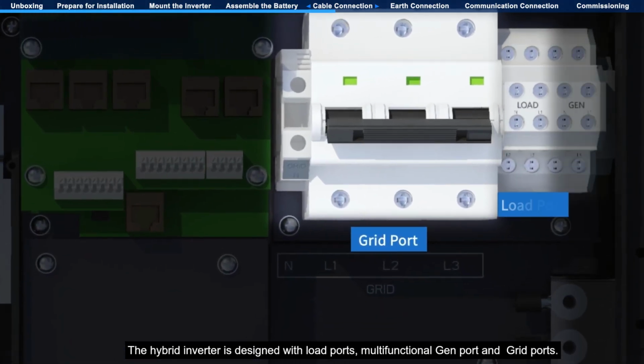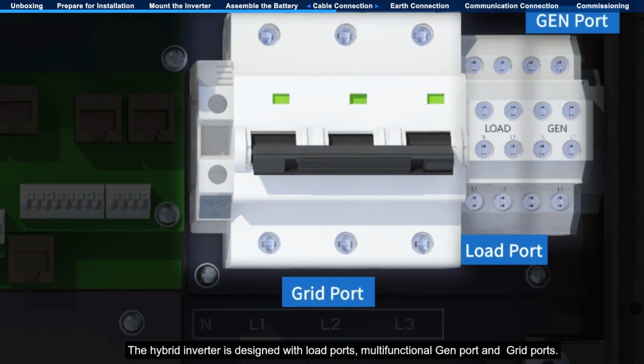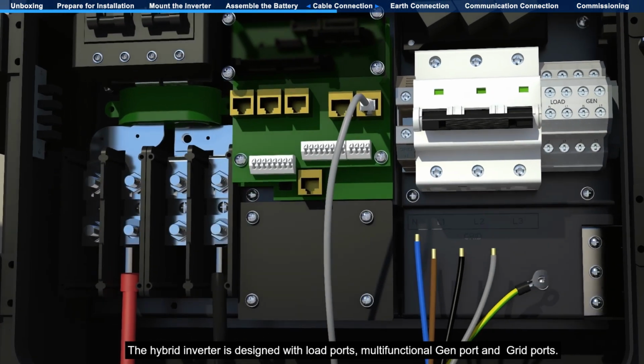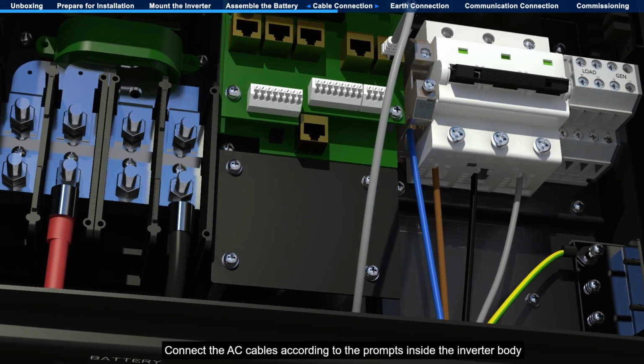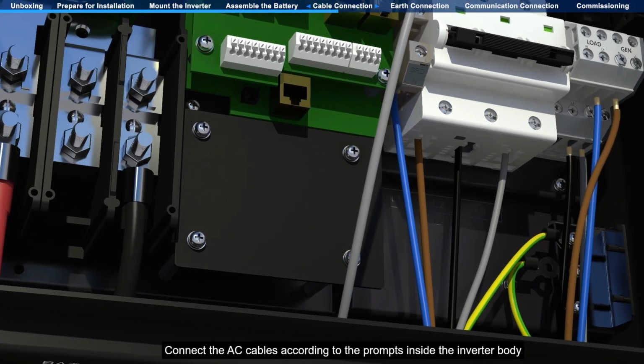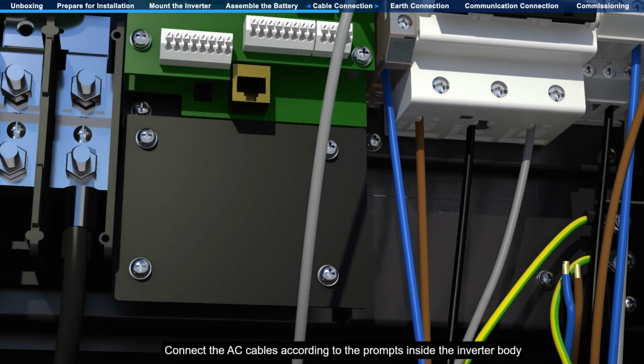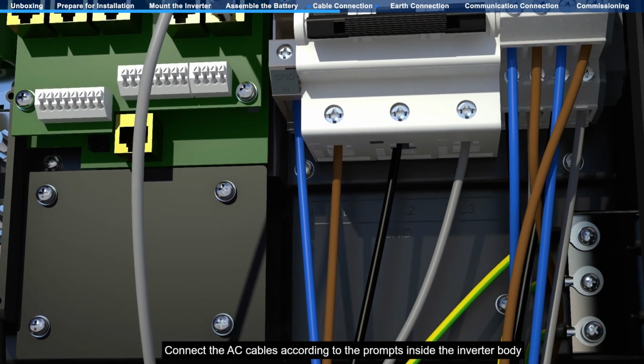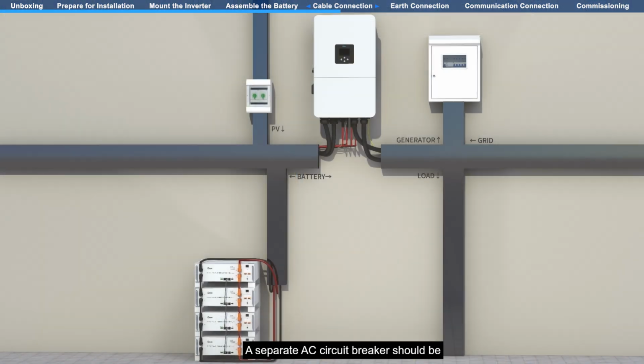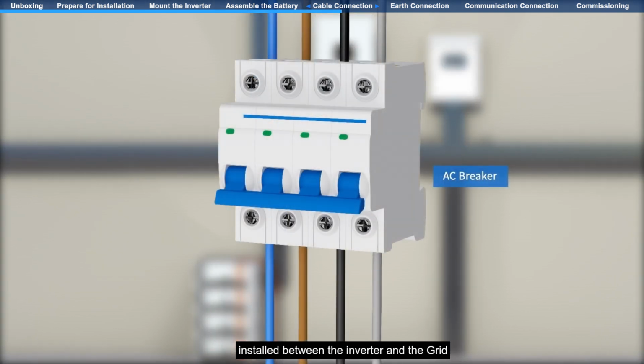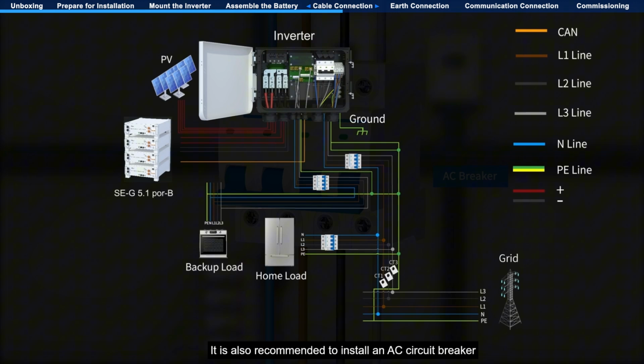AC cable connection. The hybrid inverter is designed with load ports, multifunctional gen port, and grid ports. Connect the AC cables according to the prompts inside the inverter body. A separate AC circuit breaker should be installed between the inverter and the grid. It is also recommended to install an AC circuit breaker between the load or diesel generator and the inverter.